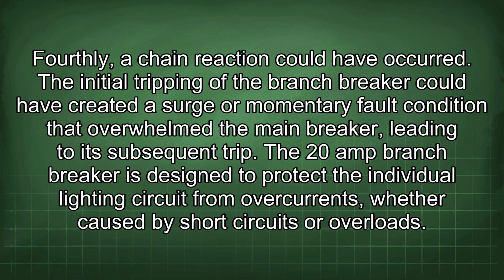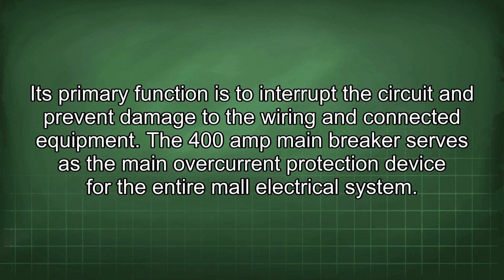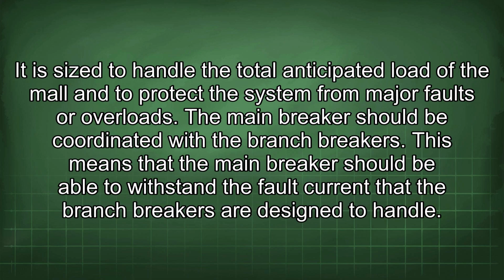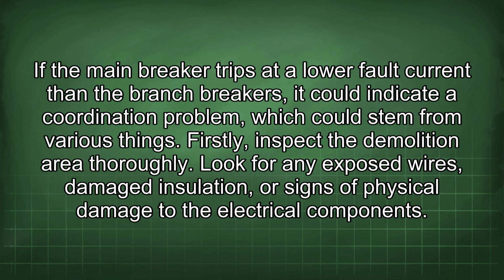The 20-amp branch breaker is designed to protect the individual lighting circuit from overcurrents, whether caused by short circuits or overloads. Its primary function is to interrupt the circuit and prevent damage to the wiring and connected equipment. The 400-amp main breaker serves as the main overcurrent protection device for the entire mall electrical system. It is sized to handle the total anticipated load of the mall and to protect the system from major faults or overloads. The main breaker should be coordinated with the branch breakers. This means that the main breaker should be able to withstand the fault current that the branch breakers are designed to handle. If the main breaker trips at a lower fault current than the branch breakers, it could indicate a coordination problem, which could stem from various things.